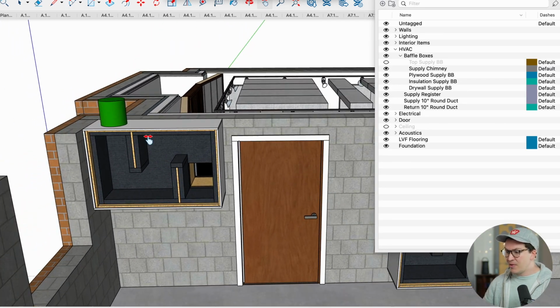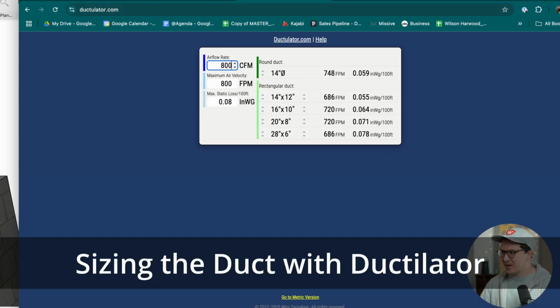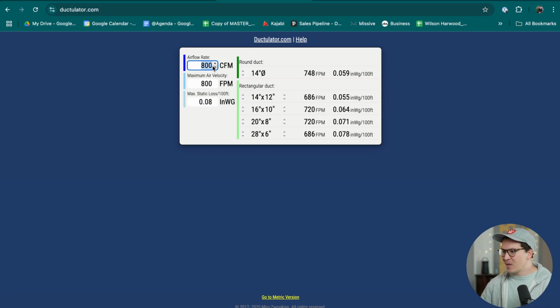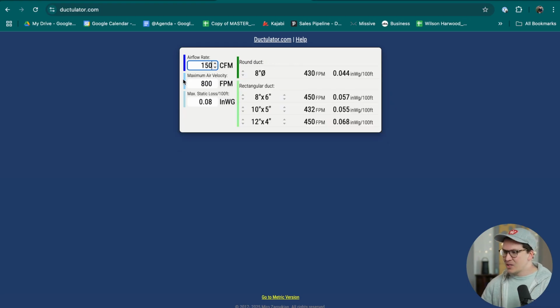Now, because this is 150 CFM, what we need to do next is figure out our Ductulator, which is this cool little thing. You can go to Ductulator.com and basically say, okay, we know our airflow rate is going to be 150. So that's what we just figured out. We're doing 150 CFM. The maximum air velocity, we always want it to be 300 or less. So 300 feet per minute, or ideally less if we can get away with it. Static pressure I usually leave at 0.08. That's totally fine. I've read that 0.1 max static loss per 100 feet, inches of water gauge, is actually totally fine for a system. So we're just going to leave that the same for now and not worry about it.